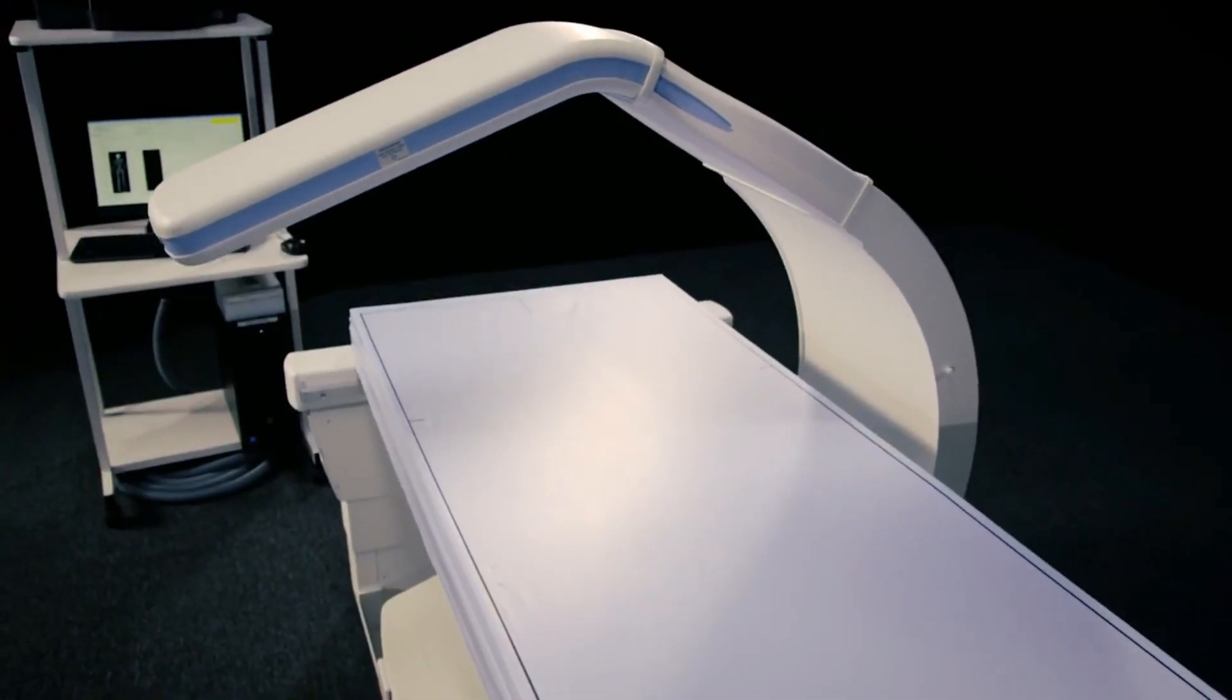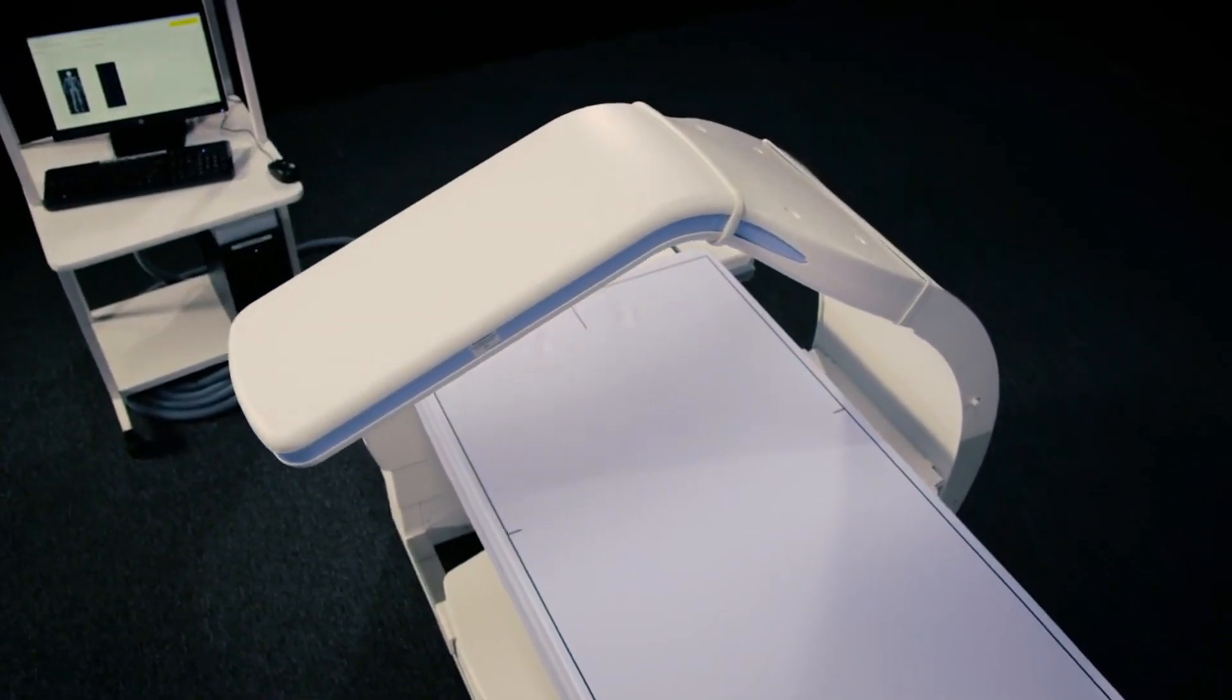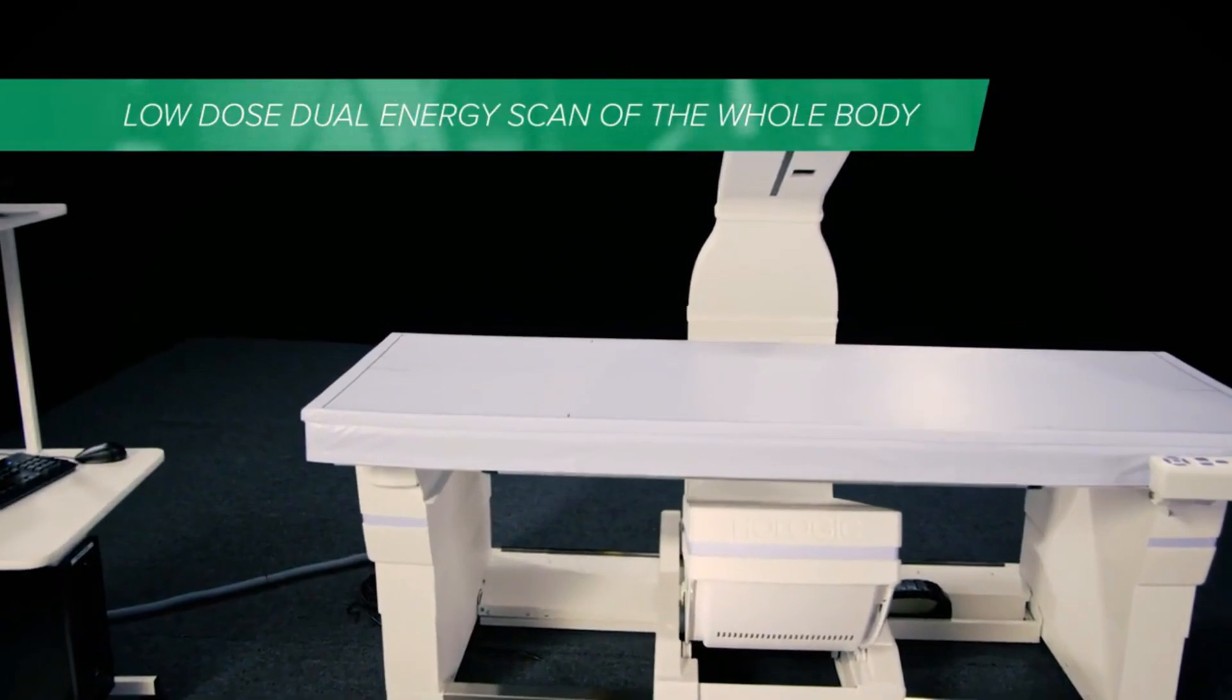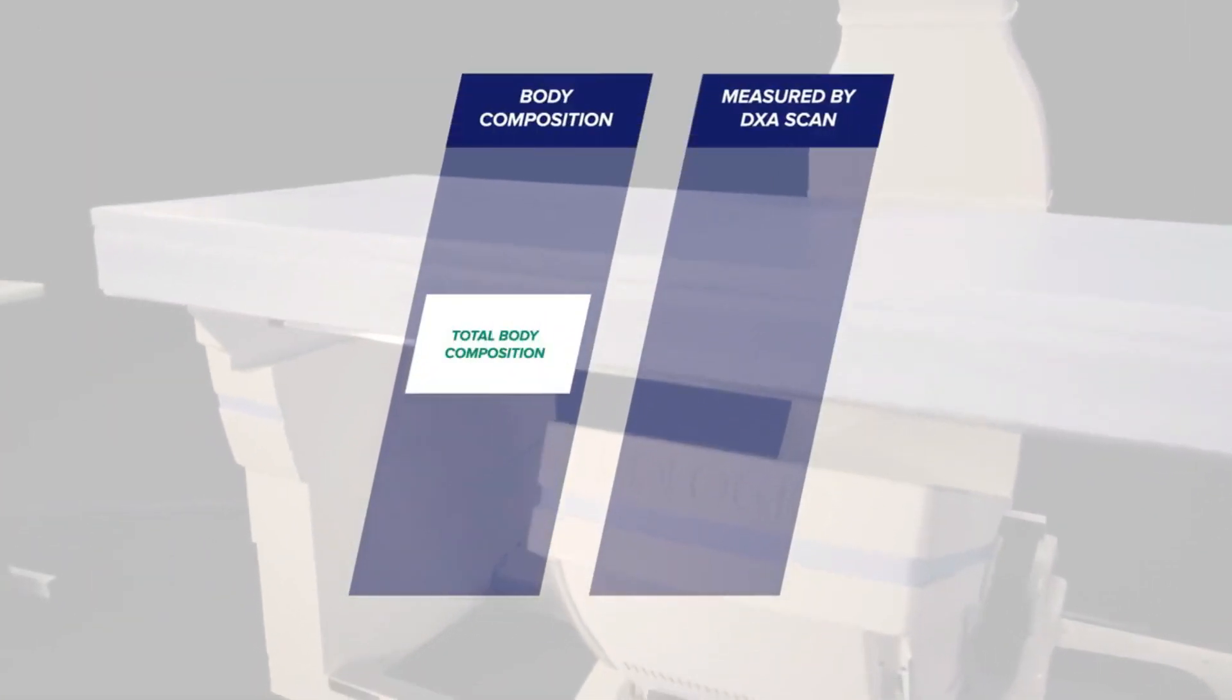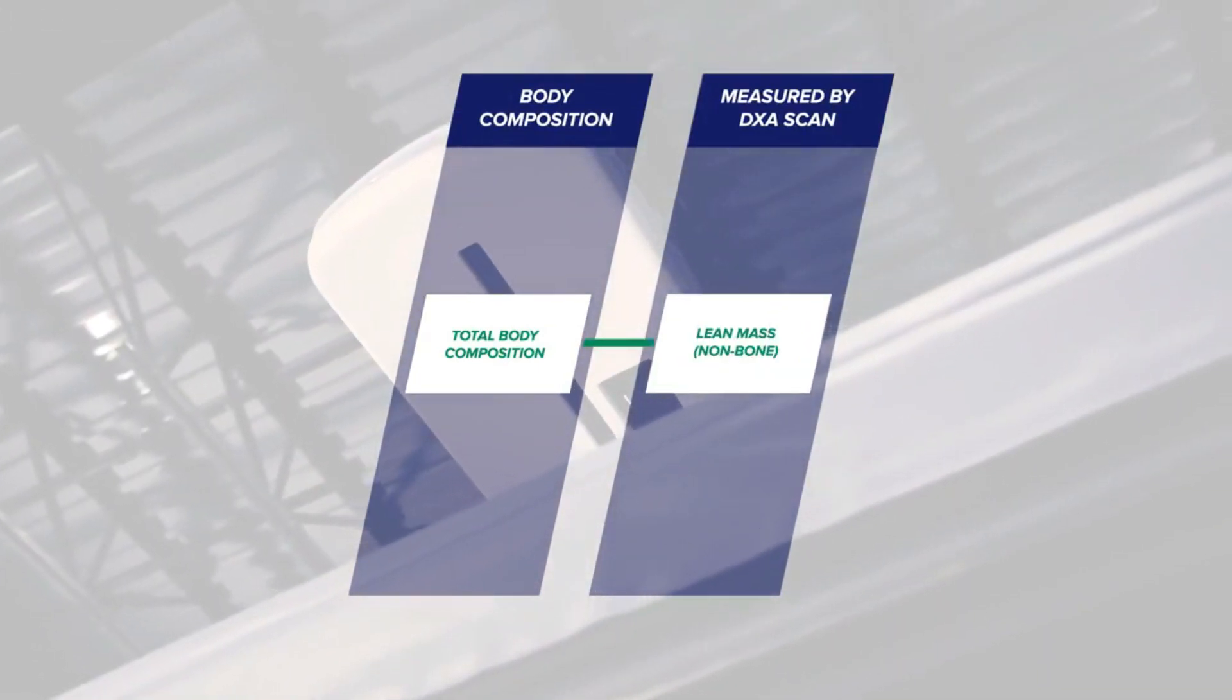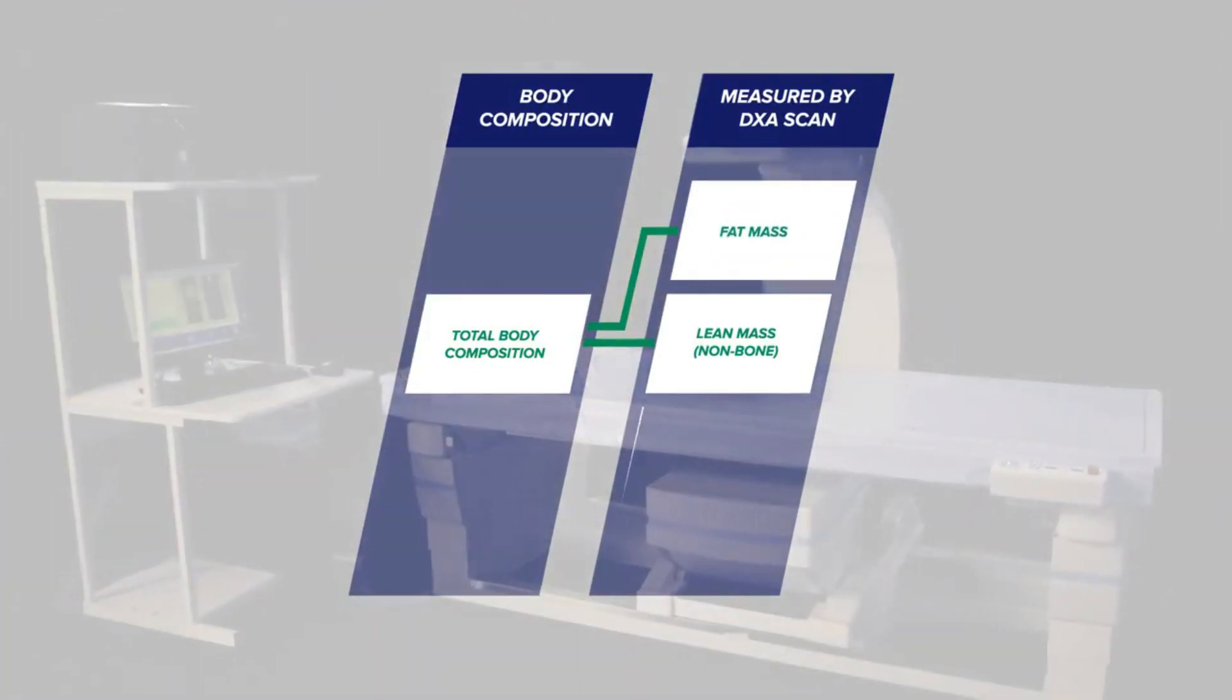This simultaneously generates two 2D images. One captures the lower-energy spectrum absorbency of the product. The other captures the higher-energy spectrum absorbency of the product. Image processing algorithms calculate the relative ratio of energy absorbed by the product at the corresponding pixels in each image, which determines an average atomic composition at that location in the product.